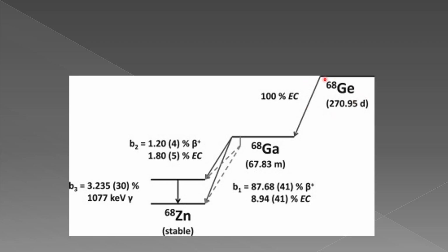We have our PET QC sources that are germanium-68. For the longest time, that's all we used them for. But germanium-68 actually decays to gallium-68. Gallium-68 is interesting because it has very, very similar tagging properties to 99m technetium. You know that we use 99m technetium for most general nuclear medicine imaging because it's really easy to tag. It tags to a lot of different things. We can form a lot of different types of bonds or ligands and things like that with technetium.